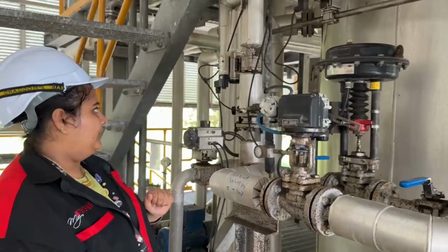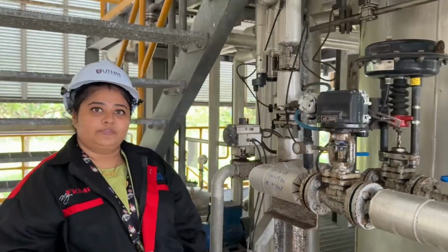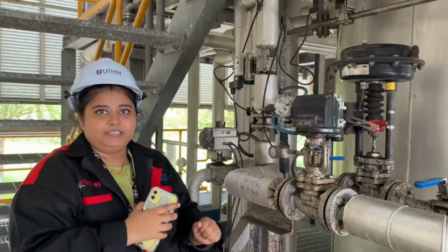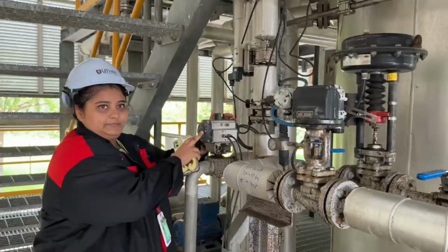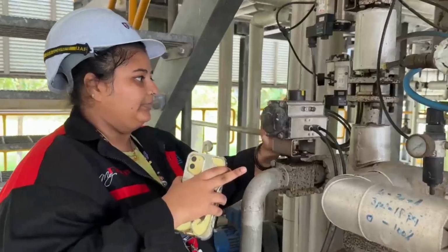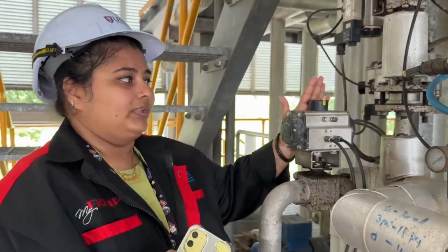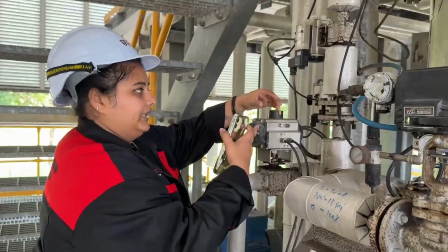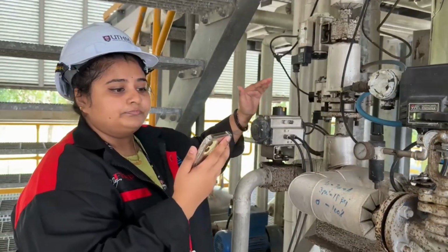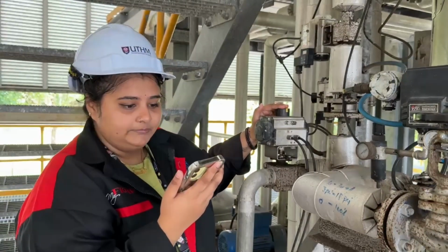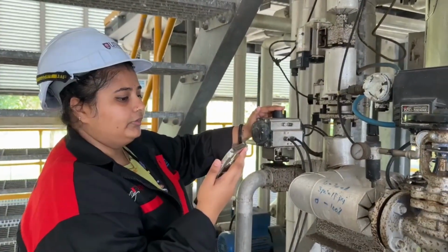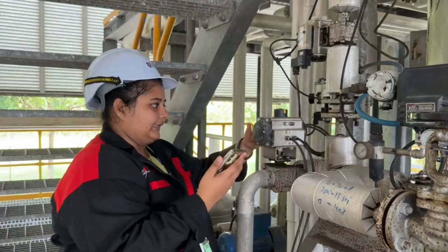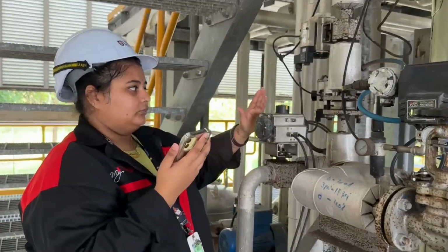Okay, so the next one is the actuator valve. Also, I've shown that in the SCADA system and also the drawing. So in this plant, we can see many actuator valves. For example, this one is an AV239B. So it's an actuator valve. It's a pneumatic actuator. This is the actuator. This is the one that actuates the valve, usually used for open and close mechanism, and it gives accurate control for the flow or pressure. In this case, it transfers liquid, so it controls the liquid.